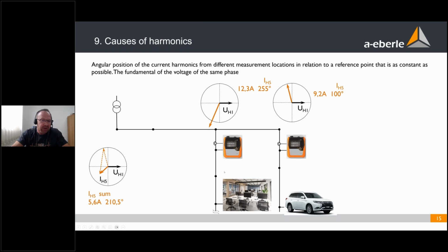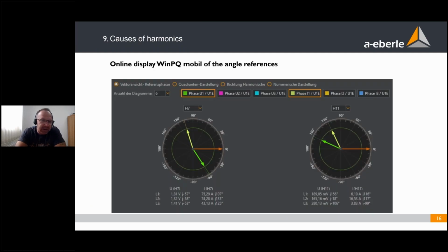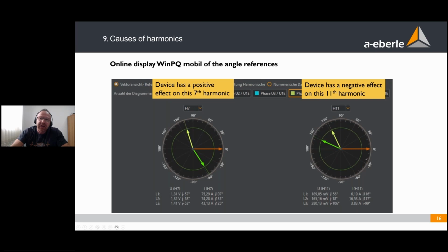So we have different possibilities to analyze the angular position of all voltage and current harmonics to see if a customer connected to the grid is positive for harmonics or negative. So it's the same here in our online measurement. We have it online and offline. Yellow means this is a voltage of the 11th harmonic at the moment in the grid. The green arrow is a current with the angle compared to the fundamental of the voltage. And if these are close together, you can imagine that this customer or this device has a negative effect on the 11th harmonic because he will increase this level in the network here.